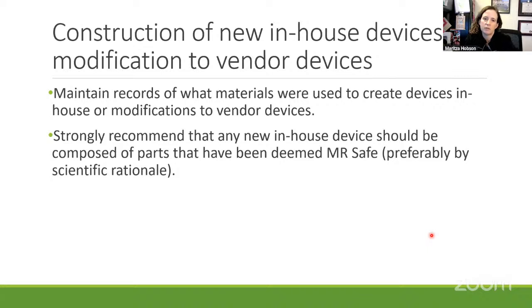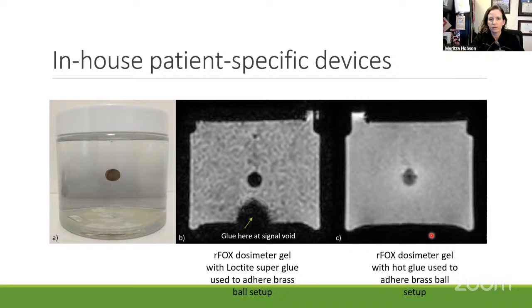So, construction of new in-house devices or modifications of vendor devices. If you do either of these, you need to make sure you maintain records of what materials were used to create devices in-house or modifications to vendor devices. And if there's any new in-house device that you're going to be constructing, you should make sure you evaluate it for bore clearance, again, including the patient size. And we strongly recommend that it not possess any additional MR safety or imaging artifact concerns. Then it's just easier on you in the long run. And we strongly recommend that they are made out of parts that are MR safe, preferably by scientific rationale. Okay. Oops. Anyway.